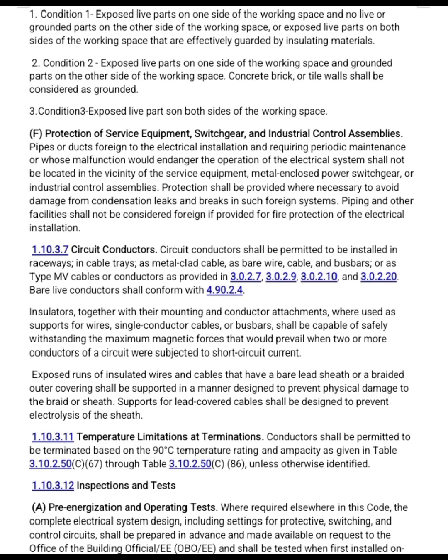Condition 1. Exposed live parts on one side of the working space and no live or grounded parts on the other side of the working space, or exposed live parts on both sides of the working space that are effectively guarded by insulating materials. Condition 2. Exposed live parts on one side of the working space and grounded parts on the other side of the working space. Concrete, brick, or tile walls shall be considered as grounded. Condition 3. Exposed live parts on both sides of the working space.